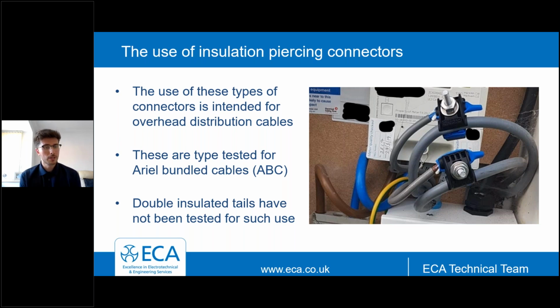So in the example here, we've got double insulated tails. Now, double insulated tails have not been tested for this use. So if you, as the designer or the installer, elect to use these type of connections on double insulated tails, you would be using them outside of their product standard, and then you, as let's say the installer, would absorb responsibility for this. So again, it's using something potentially outside of what it's been designed and tested for. And of course, if it's not making the connection it's been designed for, I guess it runs the risk of buildup of heat and may introduce a chance of thermal effects and potentially fire. So again, ECA would advise against this practice.